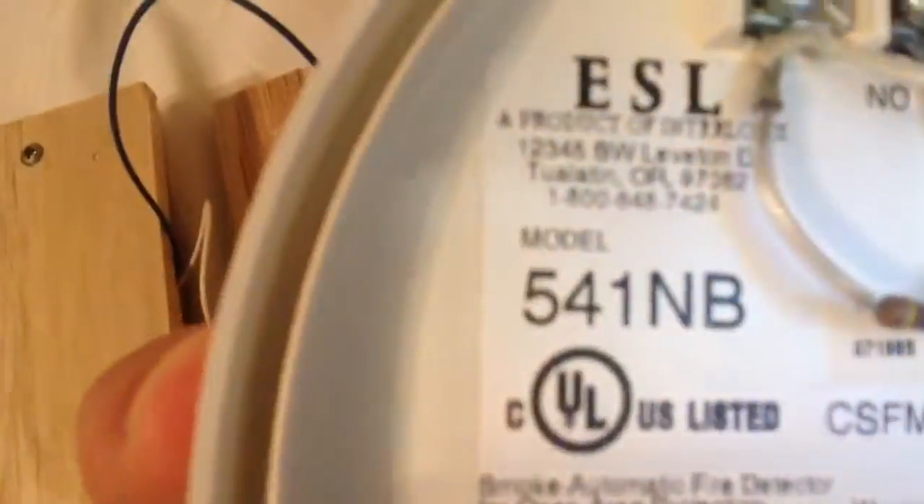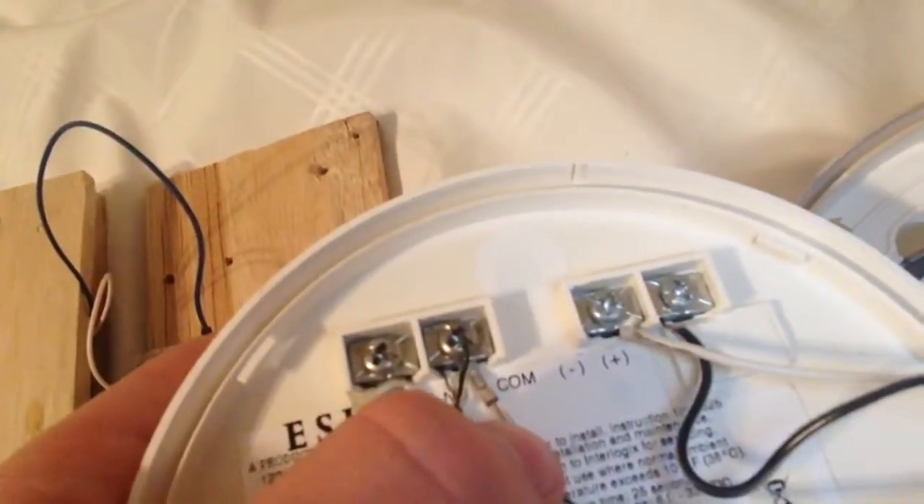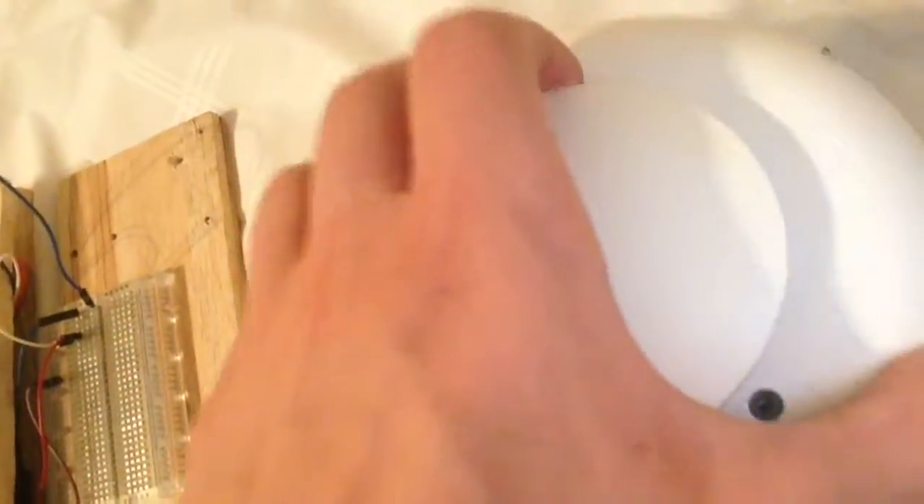Now let's have a look inside this detector. It is a hard-wired detector. As you can see, 541NB by ESL. This is also made by GE — General Electric, something like that. I do have a resistor in there, even though that's not doing anything right now. If I were to remove these wires, the panel would not go into supervisory. I did get rid of the end of circuit module — sneak peek — and set it back to the normal kind of configuration.